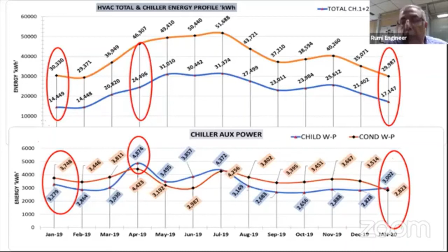Another thing—if you see how the chiller consumption varies, the pump doesn't follow the same trajectory or profile. In June, my consumption was a maximum of 30,000 units, but my pump consumption was the minimum. Yet in April, for only 24,000, my pump consumption was nearly double at 4,800. These are all the things we look at.